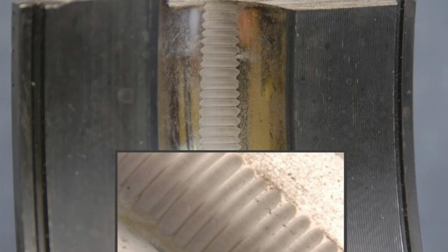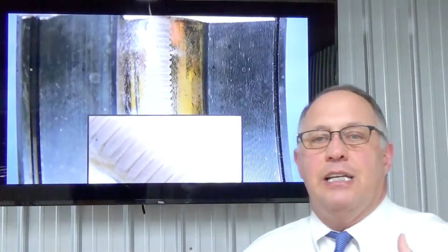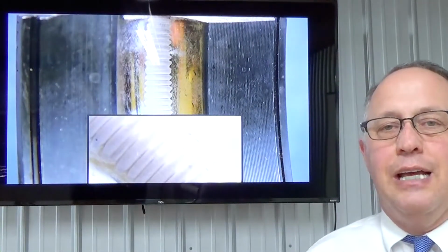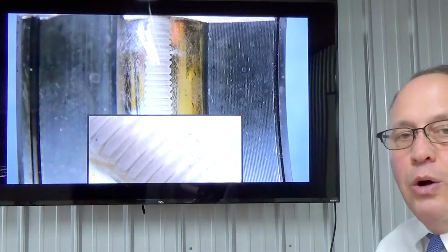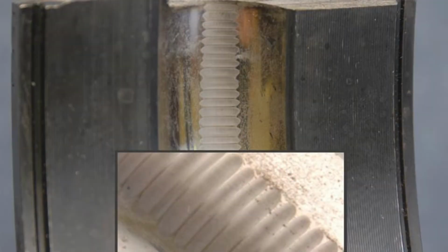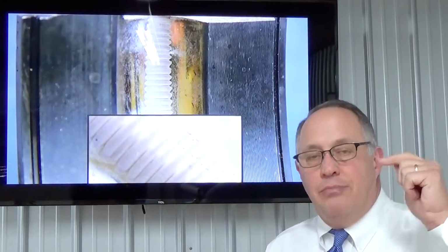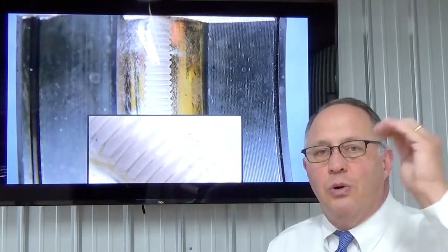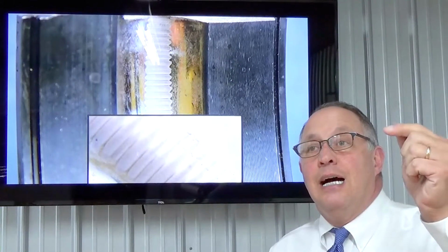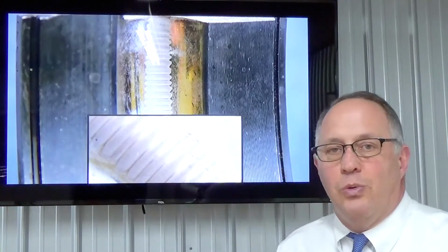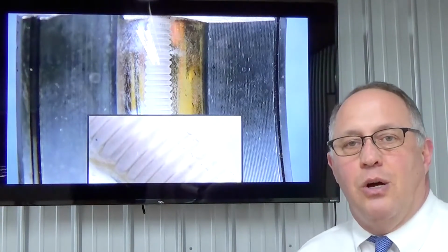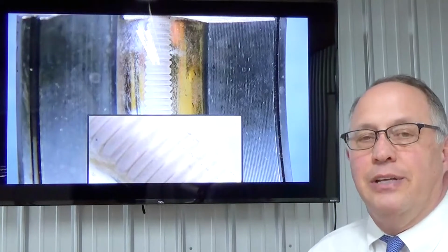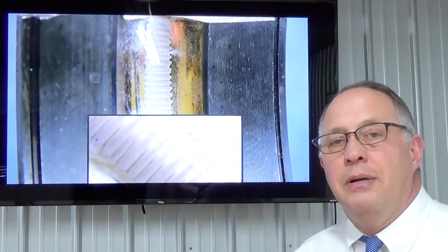The bearing failures themselves, this is actually a bearing that has been cut open, and we're looking at the raceway. You'll notice, and we'll talk about this a little bit later, the fluting washboard type effect that's caused. That's actually as a result of the frequency, each flute based on the frequency we're operating, where the bearing has suffered discharge voltages that cause the damages along the way. This is what it looks like on the inside if you actually open it up and take a look.